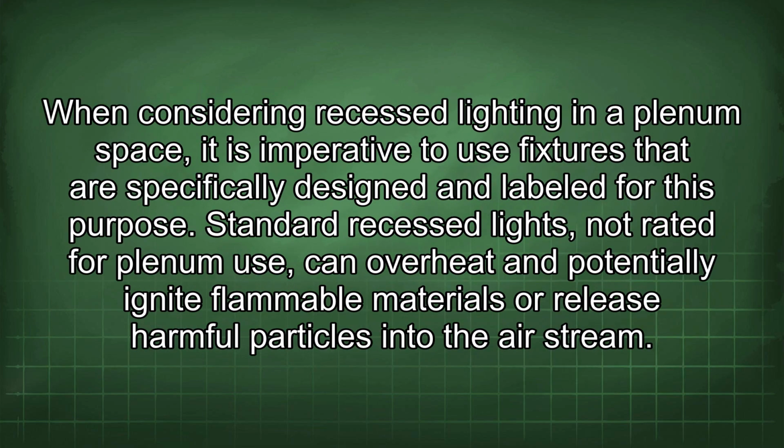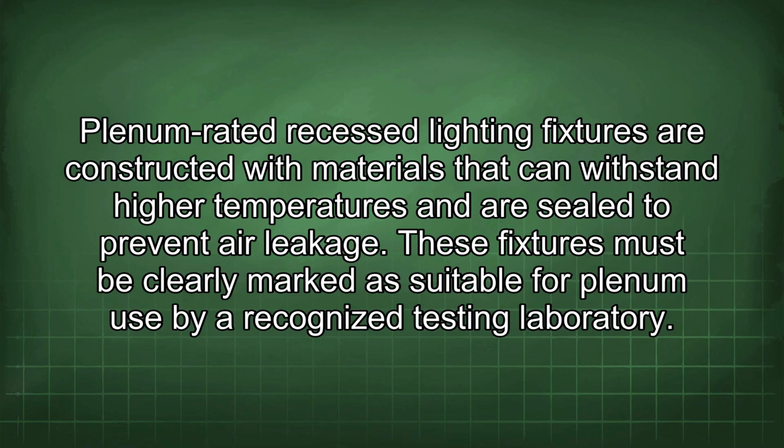When considering recessed lighting in a plenum space, it is imperative to use fixtures that are specifically designed and labeled for this purpose. Standard recessed lights, not rated for plenum use, can overheat and potentially ignite flammable materials or release harmful particles into the airstream. Plenum-rated recessed lighting fixtures are constructed with materials that can withstand higher temperatures and are sealed to prevent air leakage. These fixtures must be clearly marked as suitable for plenum use by a recognized testing laboratory.